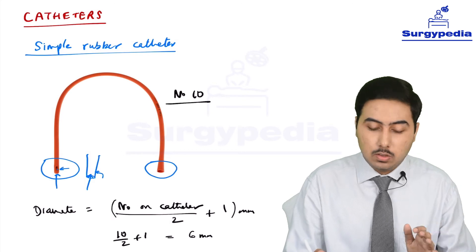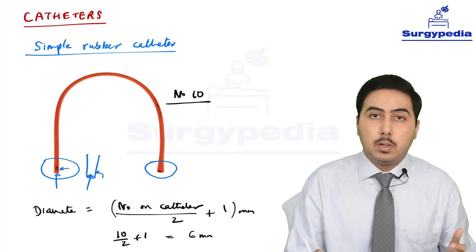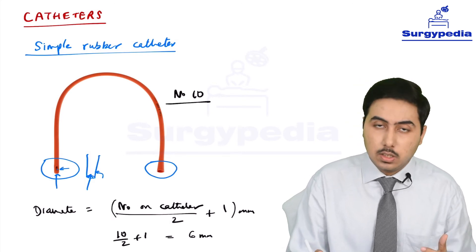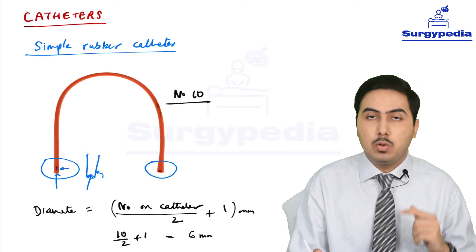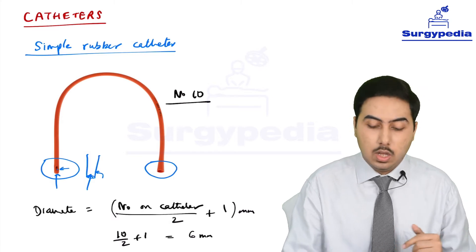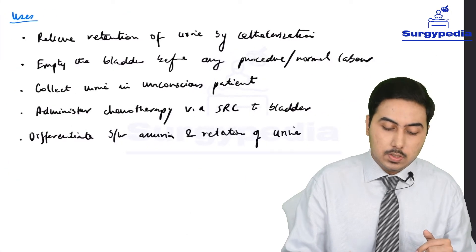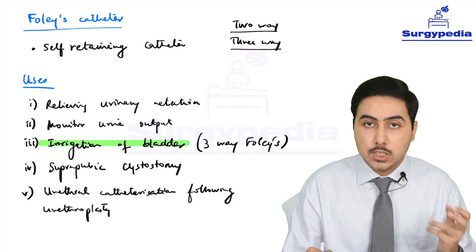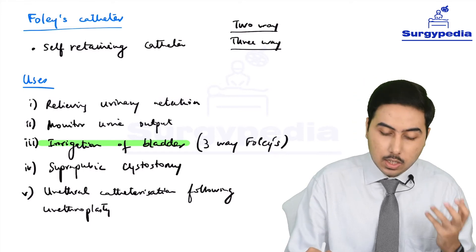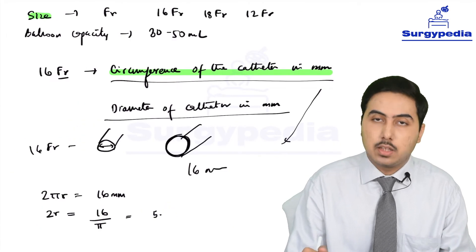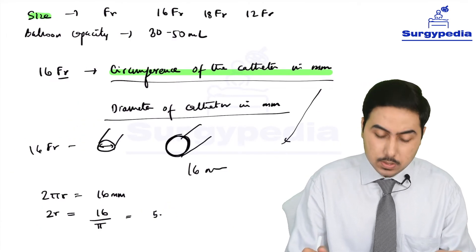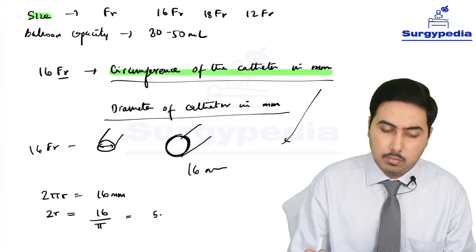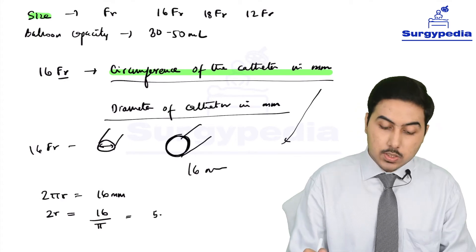The measurements of catheters are quite complicated. To summarize: for the English scale (simple rubber catheter), no FR is written — for example, number 10 — and the diameter equals the number divided by 2 plus 1 mm. For Foley's catheter, FR is written indicating the French scale, and that number represents the circumference of the catheter in millimeters, so you divide by π (3.14) to get the diameter.